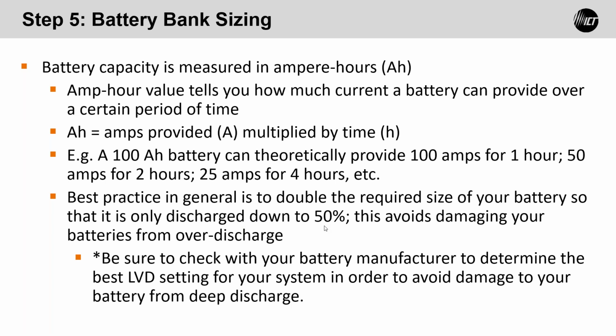And the reason for that is because the lead acid battery does not like to be deep discharged. What you need to do is check with your battery manufacturer to find out where you need to set the LVD, the low voltage disconnect, for the battery. It depends on how often your site goes down, how often you need to use the battery.